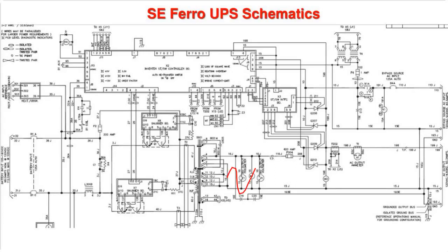So once again, a nice, beautiful sine wave coming out here. Then that goes through fuse F204 into our inverter static switch. As I said earlier, a static switch is actually just two SCRs back to back. All we have to do is send a continuous signal to the gates of these SCRs, and it will allow that sine wave to pass through. As long as we're sending a signal to these SCRs, the sine wave will pass through. We're not sending a signal to the bypass SCR. So yes, we will have power available at this point here, but it's as if this switch is off. Remember, there are no moving parts in a static switch.